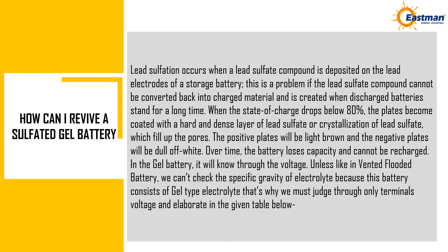Lead sulfation occurs when a lead sulfate compound is deposited on the lead electrodes of a storage battery. This is a problem if the compound cannot be converted back into charged material, and it is created when discharged batteries stand for a long time. When the state of charge drops below 80%, the plates become coated with a hard, dense layer of lead sulfate (crystallization), which fills up the pores. The positive plates will be light brown and the negative plates will be dull off-white. Over time the battery loses capacity and cannot be recharged. In a gel battery, this is detected through voltage, since we cannot check the specific gravity of the electrolyte as it is gel type.